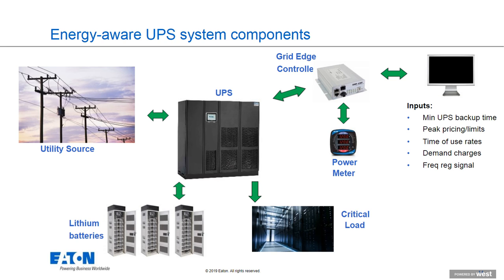But it basically can be used to control the UPS based on either a user's inputs or a combination of the user's inputs and inputs from the utility company. And of course, there needs to be a precision power meter somewhere in this scheme so that you can look immediately and see how much power is being provided by the UPS, how much is being provided by the battery, how much by the utility, what's the balance at any point in time.